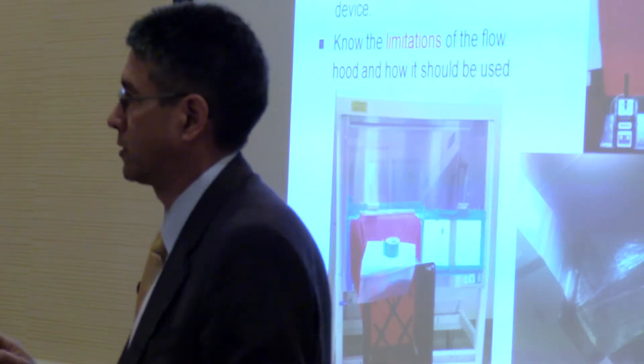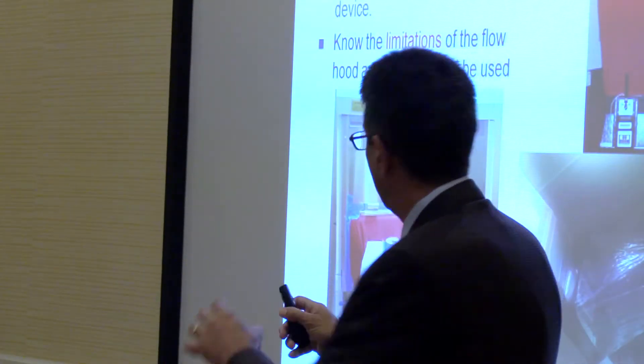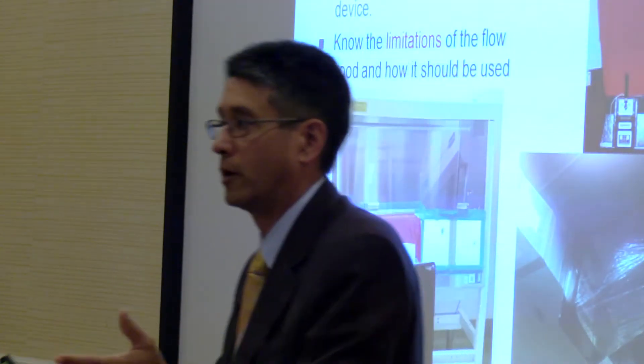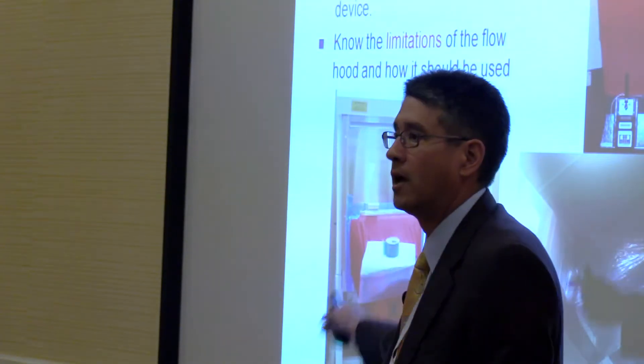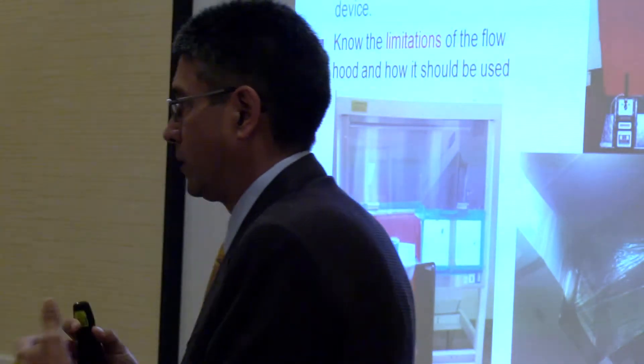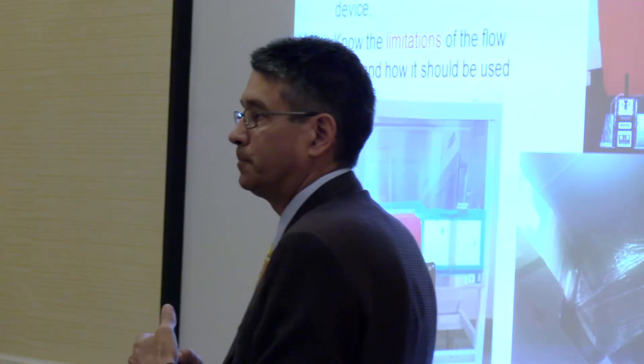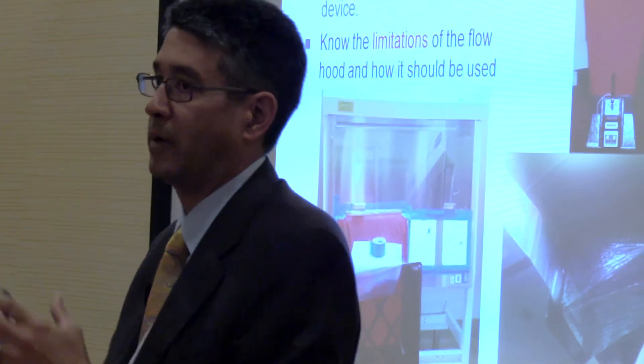Frustration in life: when you look at fume hoods and biosafety cabinets, there are organizations that tell you to put your flow hood up and measure — get a custom-made hood that's 18 inches high, four feet wide. But I don't think that's how the fume hood is going to be measured in practice. Don't always think the flow hood is a magical device — just because it says CFM on the display doesn't mean that's truly the CFM.